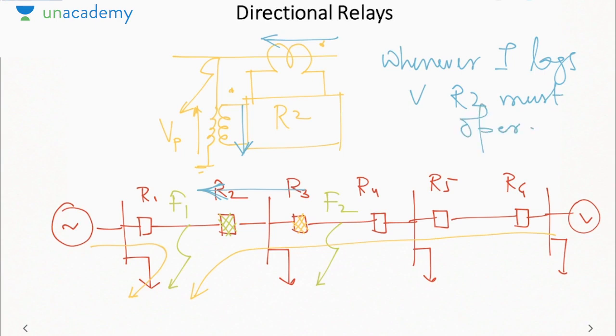But then it can be argued that the relay R2 will operate even when there is a current going into this load. Like this, if a current is coming from here, it is going into this load. Then also the relay R2 will operate. So what we can do is introduce additional protection, that will be overcurrent protection. Means the relay will be called a directional overcurrent relay, which will ensure that there is a fault since a high current is flowing, and which will eliminate the maloperation of relay R3 and ensure that relay R2 only operates. So the essential condition is whenever current lags the voltage, the relay will operate, but it is understood that the current must be higher than a preset value or a pickup value.